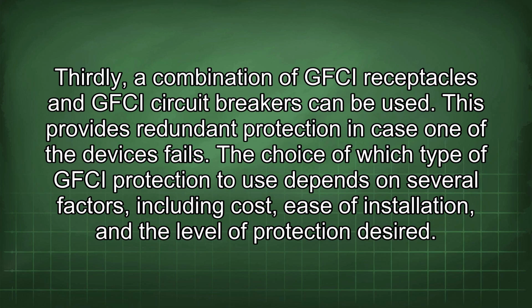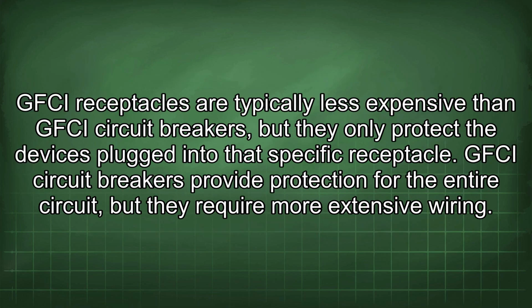The choice of which type of GFCI protection to use depends on several factors, including cost, ease of installation, and the level of protection desired. GFCI receptacles are typically less expensive than GFCI circuit breakers, but they only protect the devices plugged into that specific receptacle. GFCI circuit breakers provide protection for the entire circuit, but they require more extensive wiring.